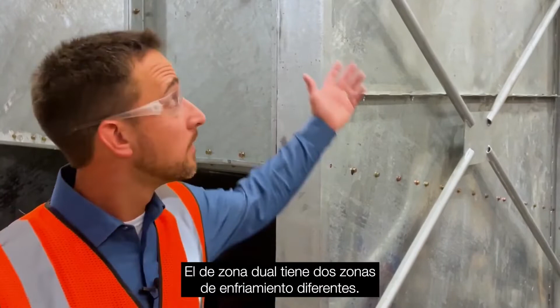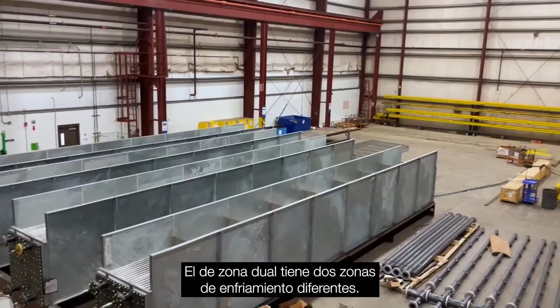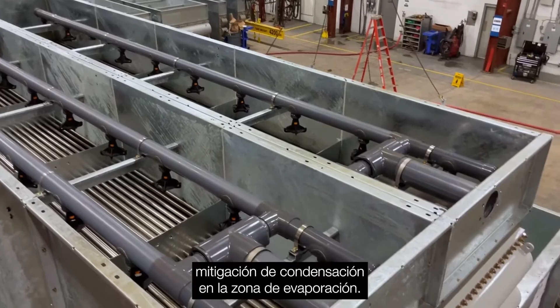Our dual zone has two different cooling zones. The first is a traditional air-cooled heat exchanger. The second, an evaporative cooler, which adds to your overall cooling capacity. This design works best with hotter process inlet temperatures. It helps save water and energy while also providing plume abatement in the evaporative zone. So whatever application you run, we have the HYAC hybrid air cooler for you.